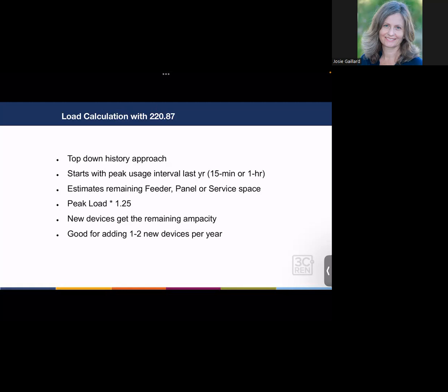the very highest electricity usage 15-minute interval or 1-hour interval across a year. Now you're going to take that peak load and figure out what was the peak power in that time period. You're going to apply a 1.25 factor. That's what the code prescribes to that peak load, and then find your new devices. And those can use up whatever remaining ampacity is left after you've done that calculation.